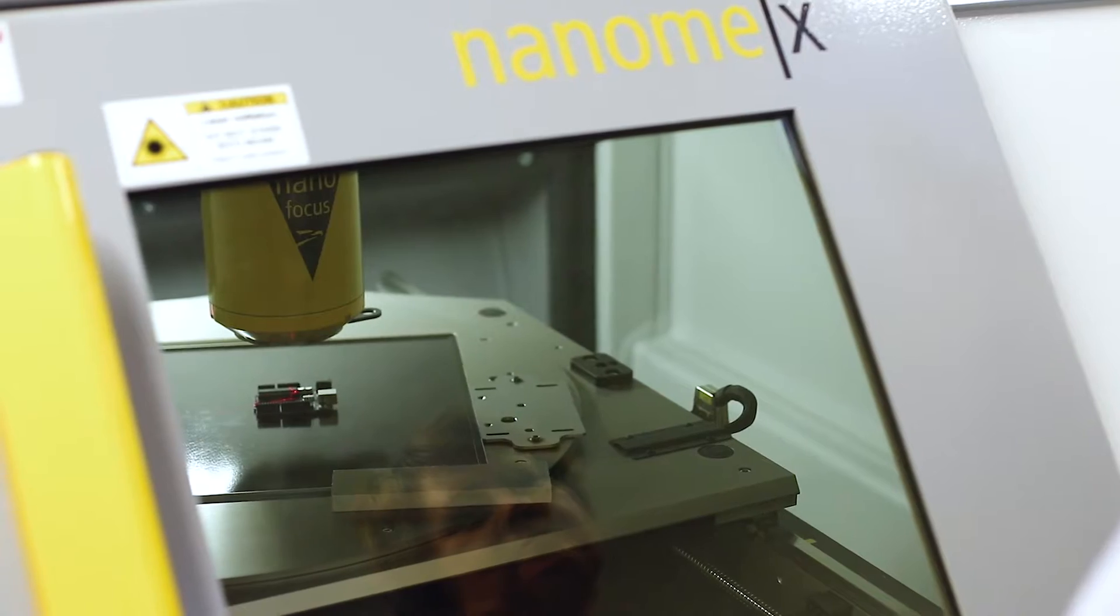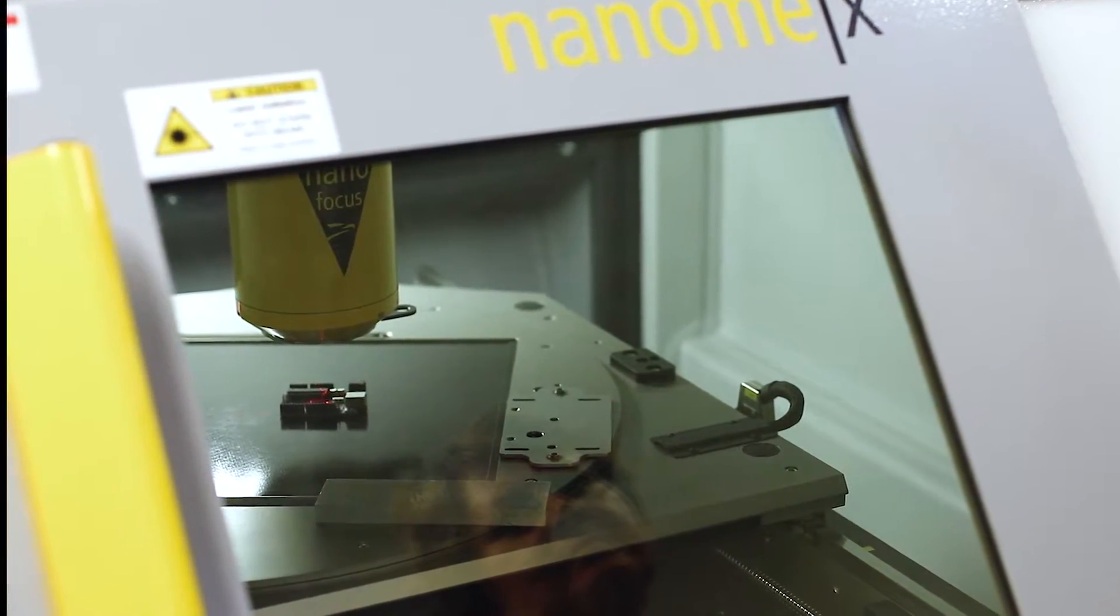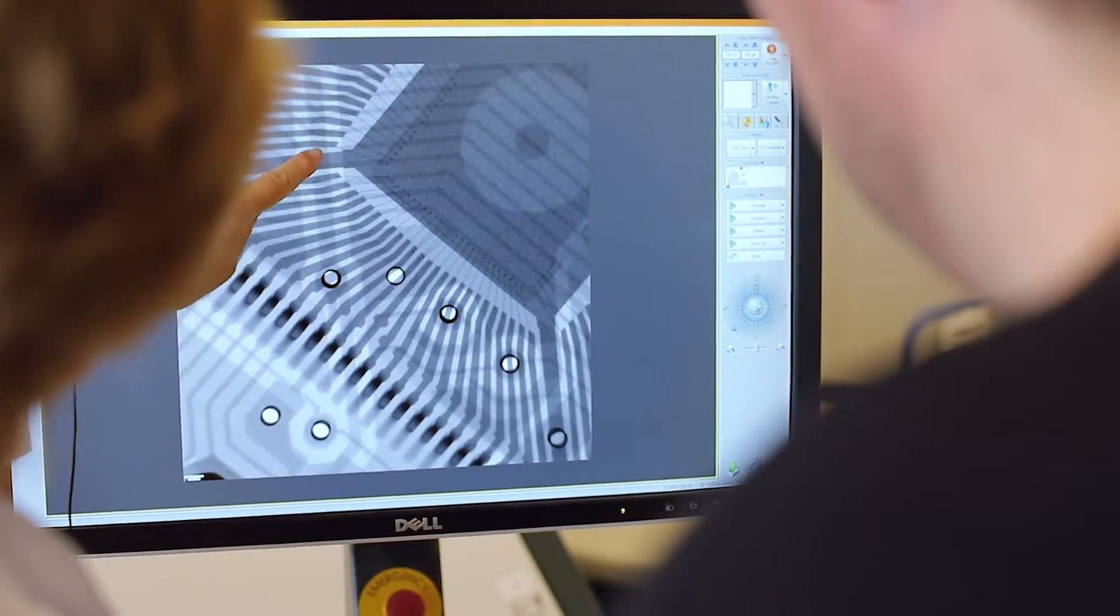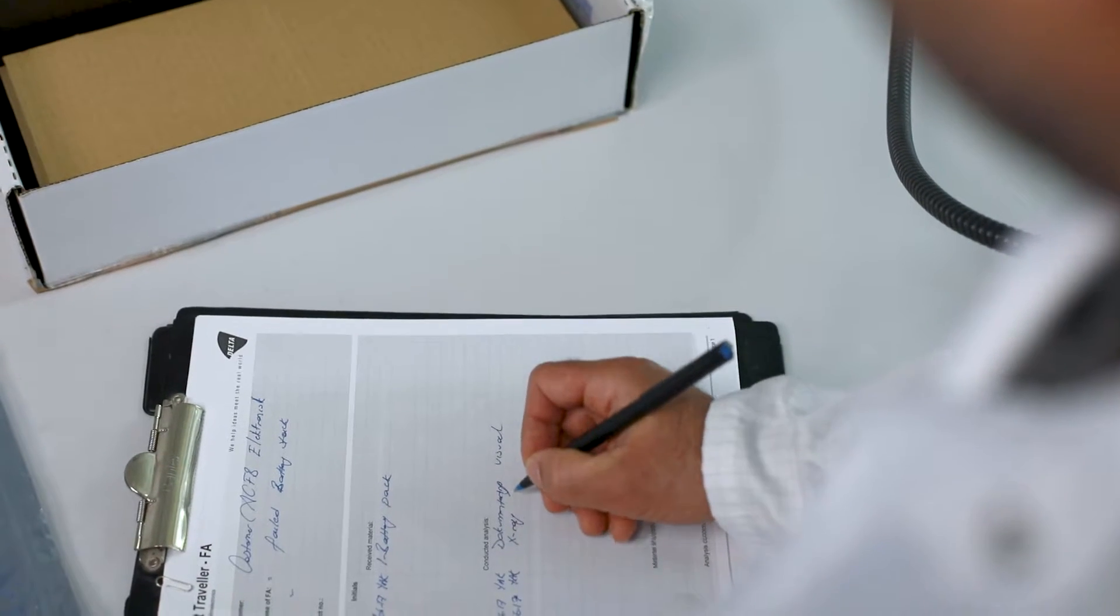We use high-resolution X-ray equipment to check for degradation and process-related issues, such as alignment problems or cold solder joints. Every finding is documented on the travel card.